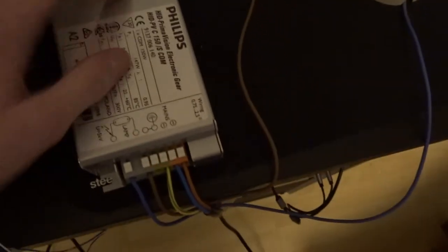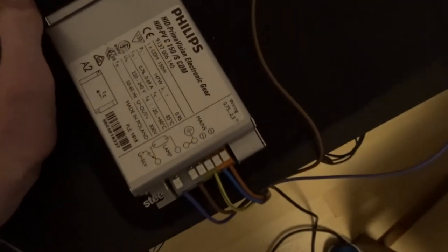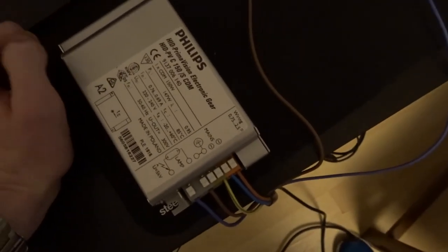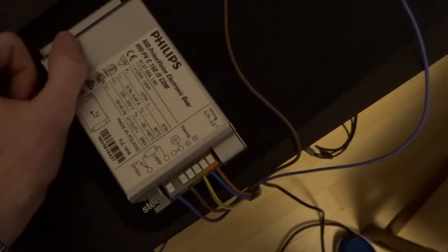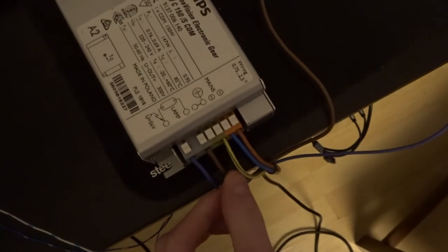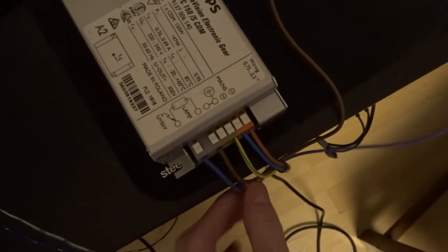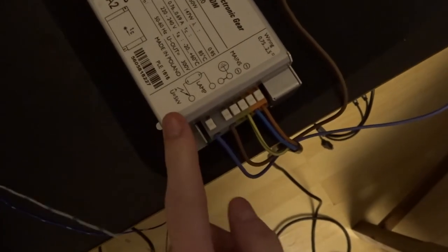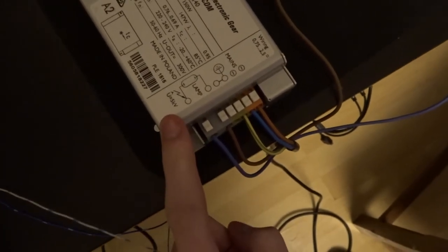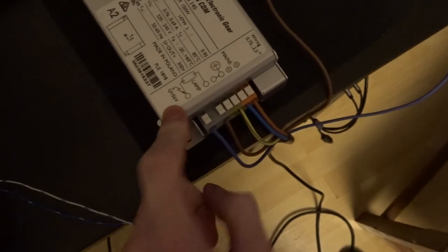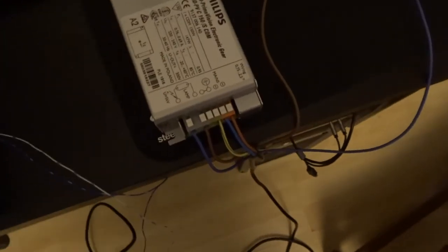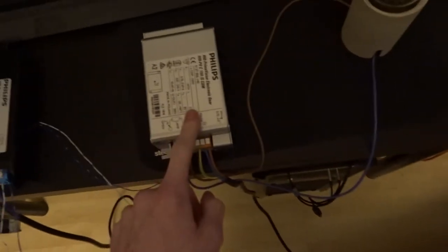Now let's get over to this one. This is the HID PrimaVision electronic gear. Again, 150 watt ballast. Mains input, earth, and then your output. And it specifies a slightly higher maximum 5kV starting voltage by the looks of it. But this one's digital as well, but there's no control for dimming. It just does maximum.